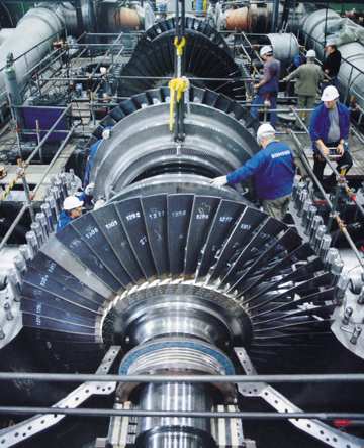In 1979, a European consortium including Siemens, Brown Boveri and Cie, and AEG realized the record HVDC link from Cabora Bassa, Mozambique to Johannesburg, South Africa, extending more than 1,420 kilometers and rated 1.9 gigawatts at plus or minus 533 kilovolts, that resorted to top-performing 3.2-kV thyristors, developed by AEG under GE's license.